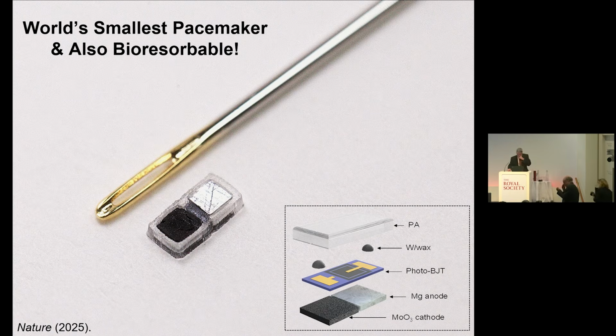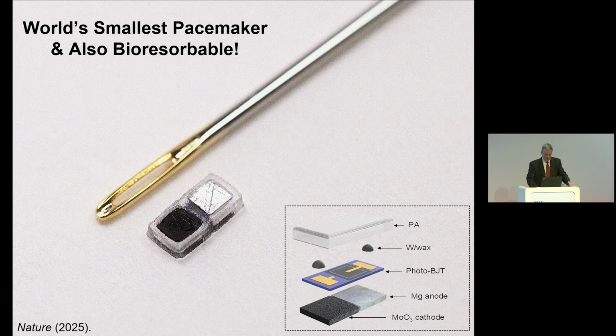So it consists of two parts, and it's all bioresorbable, by the way. It's a pair of electrodes, both made of metals that are bioresorbable, but they're dissimilar metals. So they form a galvanic pair. When in contact with biofluids, it's basically like a primary battery. So it's a battery driven by bioresorbable metal electrodes that also establish the electrical interface to the cardiac tissue. Okay, so that's the battery.